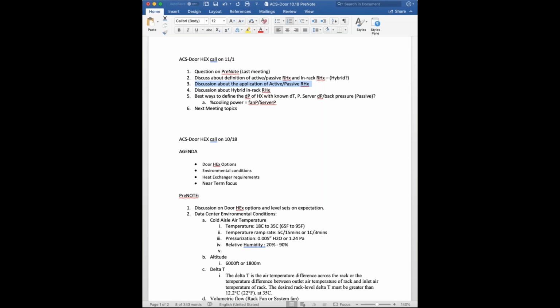I mean, one of the downsides for this concept, which I think is aligned to the hybrid, is that we're still relying on cooling the hot chips with some sort of heatsink type of solution. So although we are getting some power density benefit at the rack level for the cooling, I think the cooling at the server level is going to be quite limited with this approach.